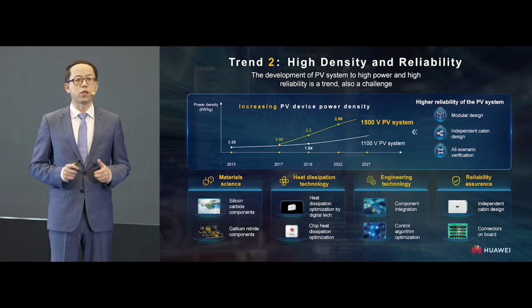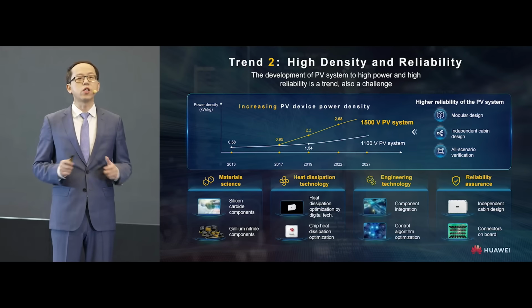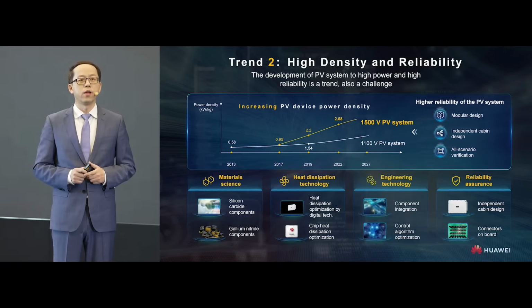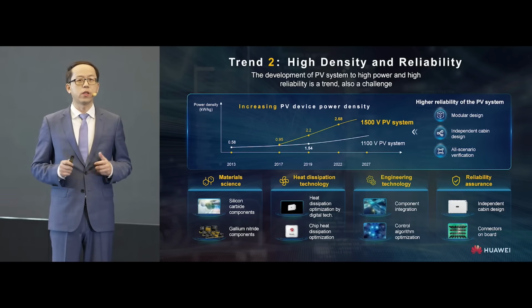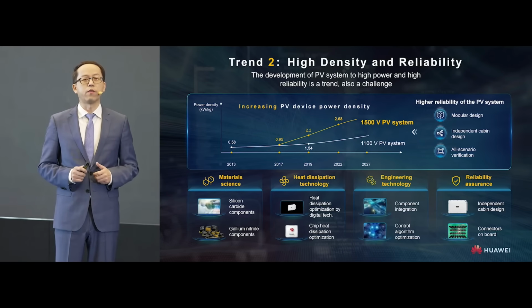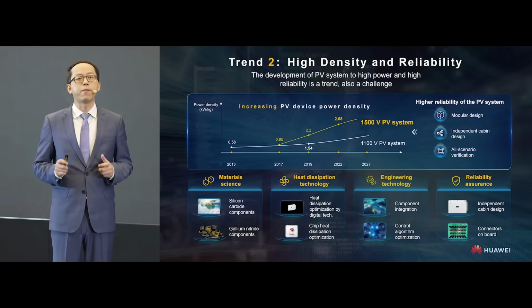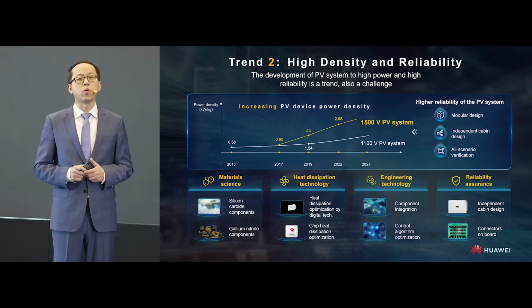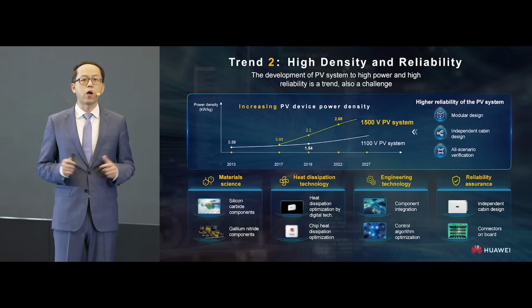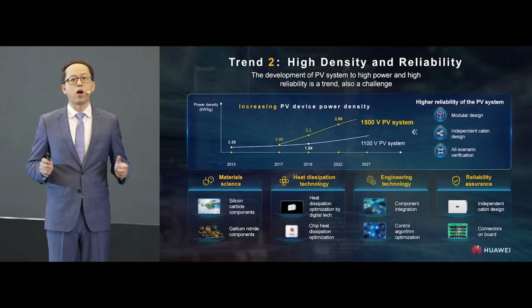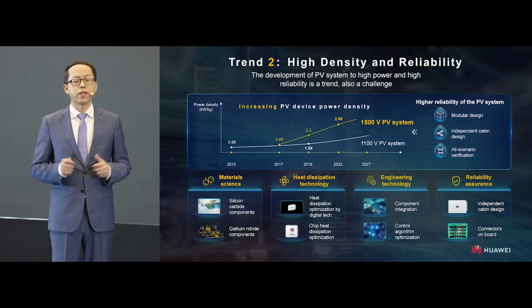After 4 years of R&D and testing, our intelligent string inverter has achieved high reliability with high power. The UHV project in Hainan, Qinghai Province is a 2.2 GW PV station consisting of 9,216 devices that operate stably in a harsh environment at 3,100 meter altitude. The service duration of inverters reaches 20 million hours, and system availability reaches 5 nines, ensuring high yield and reducing LCOE.